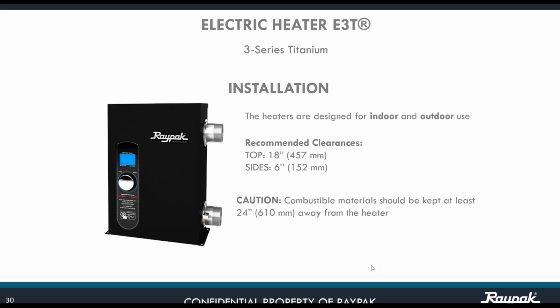Okay, spaces. The only recommendation on this one is to leave 18 inches on the top and 6 inches on the side. Remember, you need to have enough space so that if you require a bypass, you'll have the space to do so. That's the reason why we are saying that. Besides that, do not install the unit in a very confined space. Do not put it upside down, it's not going to work. And do not make the connection in a reverse way, where the outlet connection goes to the unit's inlet, because it's not going to work. Remember that there is a flow sensor that needs to sense those 15 gallons per minute in order to operate properly. So you might think, no, that is not going to happen.